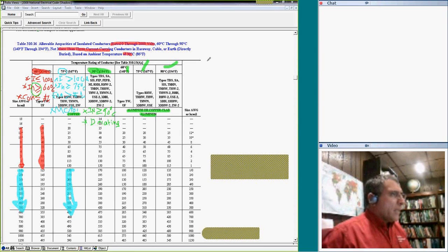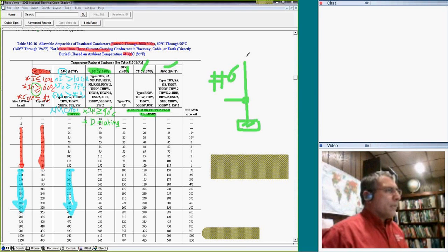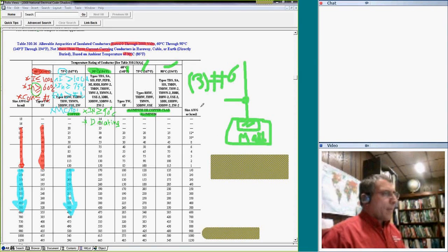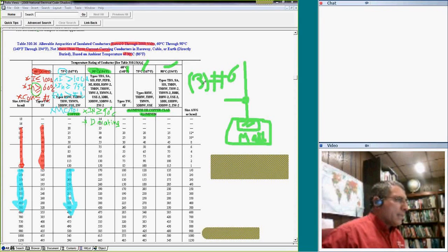So let me give you a quick example. Suppose I have number 4 conductor coming over here and tied to a lug. Current carrying number 4, and it's 3 conductors, 3 of them, current-carrying conductors in a conduit feeding a motor. Here's my motor through a lug, feeding a machine. Not a machine that welds. How much can number 6 carry under these circumstances?